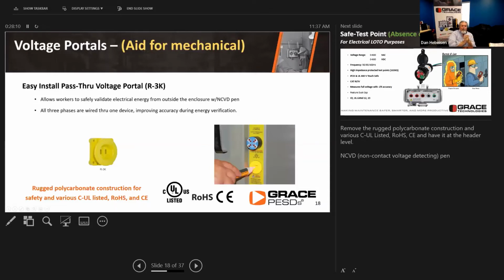An additional aid for mechanical lockout tagout is basically a pass-through voltage portal. This is really designed to utilize the opportunity of a non-contact voltage detector. Several different manufacturers make them; this particular one is manufactured by Fluke. They'll basically measure voltages from 90 volts all the way up to, I don't know, 230, 240, somewhere in that range. And it just gives you the opportunity to say, is there voltage there, yes or no?